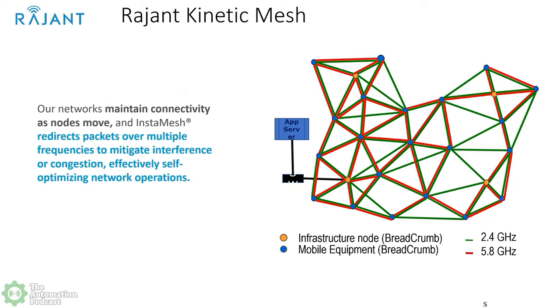They're very configurable. You can get as deep as you want when it comes to security and networking protocols — we have ways to set up a gateway, let the radios handle their own DHCP addresses, support port forwarding. But all that aside, this network is also the easiest deployable network out there today, because the nodes literally come up and mesh right out of the box before you even touch them. One thing that's relevant to your audience: not only can we transmit IP data and UDP data, we also support Modbus and serial data. And we support Profibus and Precision Timing Protocol. You can do all of that over the same network.